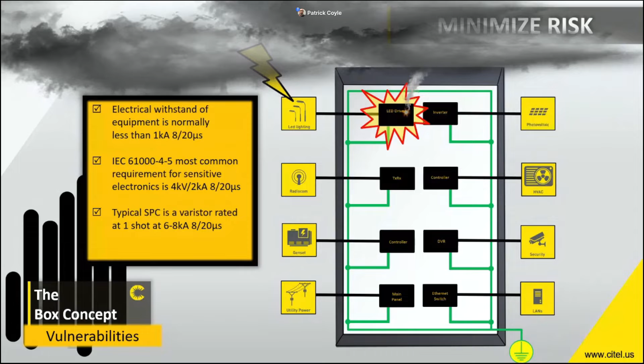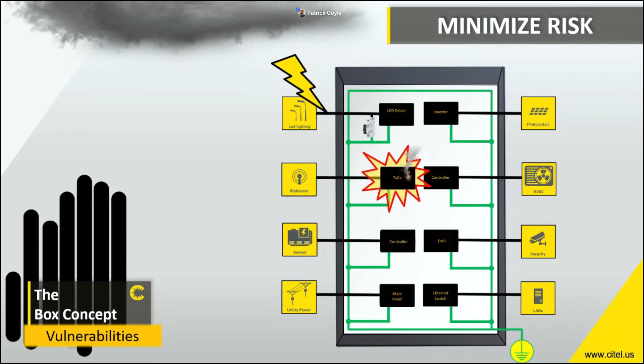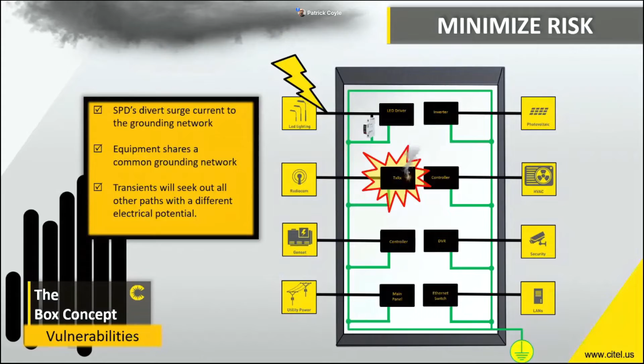You get smart. You place an SPD at the front of the entry, in front of your LED driver, and then sometime in the not too distant future, that pesky storm rolls in again. Lightning arrives as expected, travels down to your equipment, is diverted away by the SPD and put into the grounding system, and poof, there goes your buddy's wireless radio. It fails. But why? Surge protectors divert energy, they don't absorb it. And because all equipment shares the same grounding system, the surges can and will travel all available paths, searching for a good path to ground, and that could be directly through your equipment.